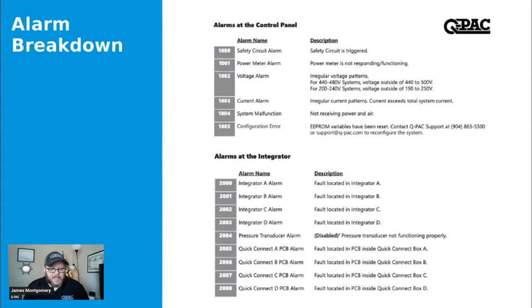We independently run the control signal, or the 0 to 10 analog run signal, to these fans. If that's intact, the fan will still run. There's two other wires in our control bundle that are affected by this. And if the PCB cannot detect the status of that fan, it could potentially still be running. You poke your head in there and say, oh, it's running, but it's an alarm. This is probably a comms issue, or maybe a wiring issue.